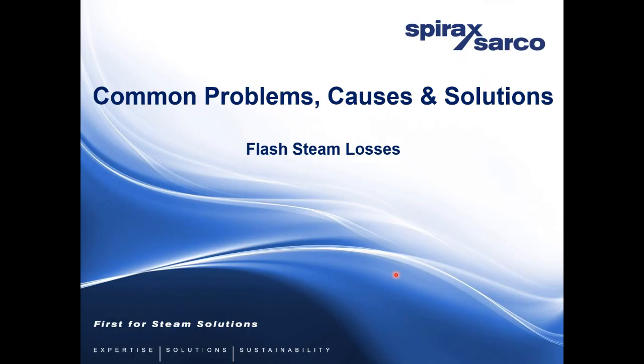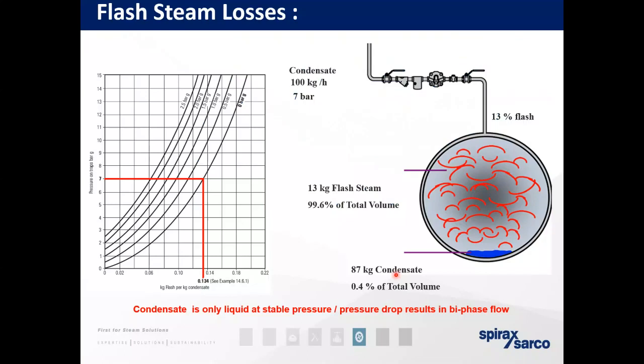So, common problems, causes and solutions for flash steam losses. As we've said before in our last webinar, the majority of what you'll see in your condensate system isn't actually water. As we show here, you have 13 kilograms of steam based on 100 kilograms at 7 bar, 13% flash. What that translates to in volume is that 99.6% of the total volume is actually flash steam. Only 0.4% of the total volume is condensate. So what we're transporting back to our feed tanks is mostly flash steam, not actually water. As you can see from the graph, this will give you the figures.